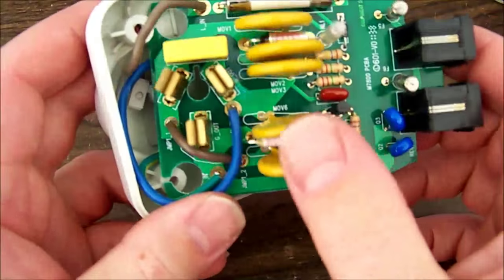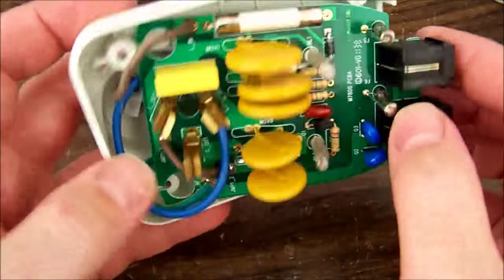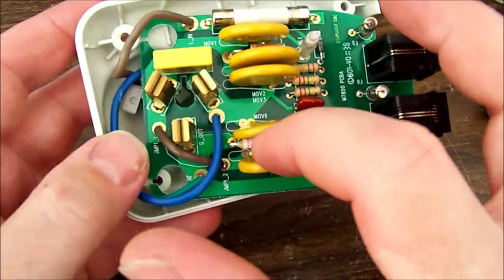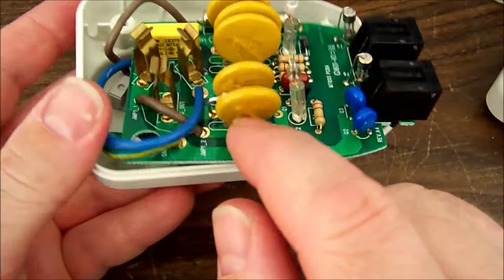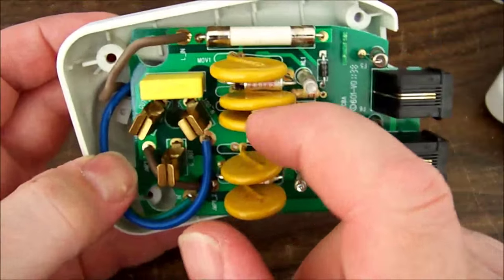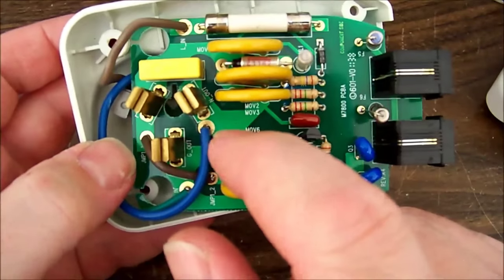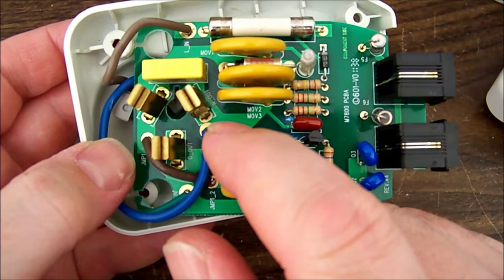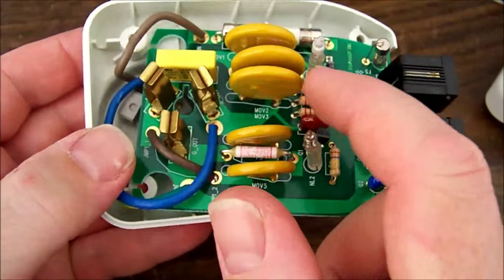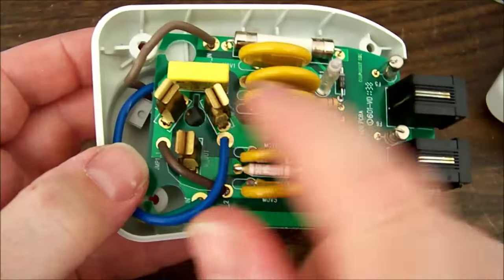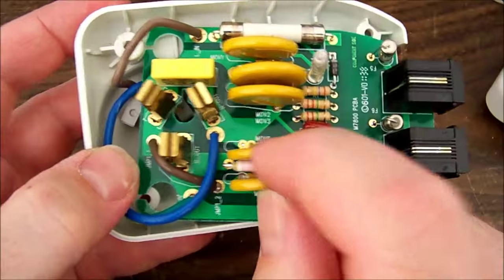Just run over it with a measuring resistance. That fuse is okay, those two fuses are okay. The MOVs are in the meg ohm range, which is what you'd expect. They don't conduct until a predetermined voltage level, at which point they almost become a short circuit to pass that fault current through.